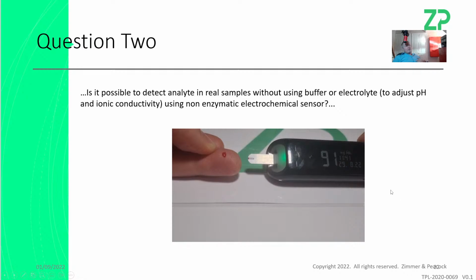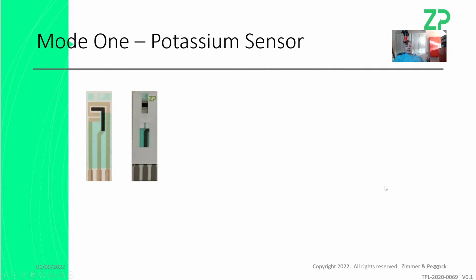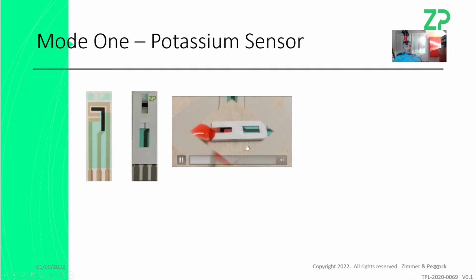Now, I'm going to slightly expand and talk about potassium sensors, because when somebody says I want to use a potassium sensor, there are much deeper questions here. Here's a potassium sensor from Zimmer and Peacock. Did you want to use it in a capillary fill mode like this? What I mean by a capillary fill mode is you take the sensor. This is an awful lot of blood. It's actually just dyed water, but there it goes.